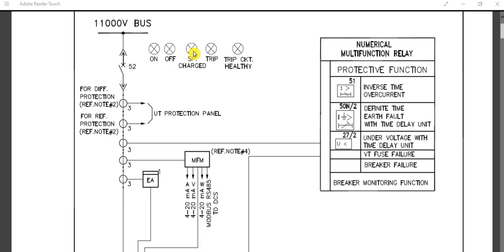Additional LED indications include: breaker tripped and trip circuit healthy. All these LED indications show the circuit breaker status — whether the breaker is on or off, whether the spring is charged, whether it has tripped, and whether the trip circuit is healthy or unhealthy.